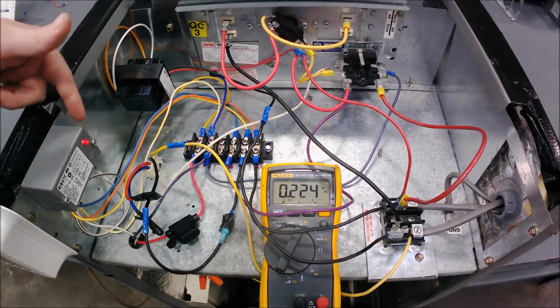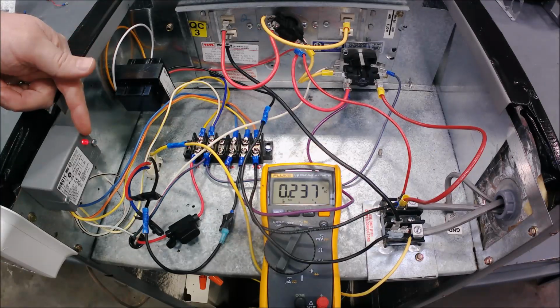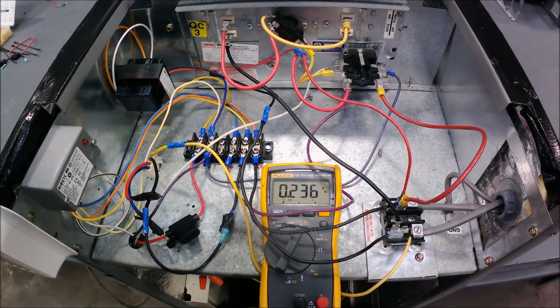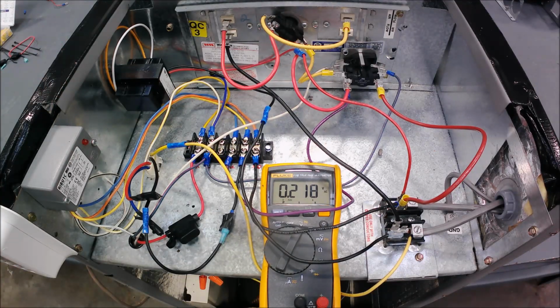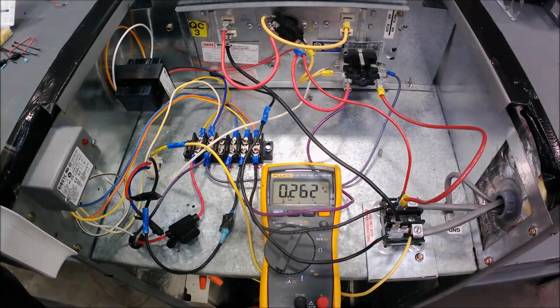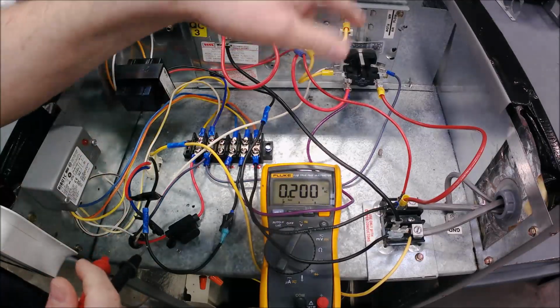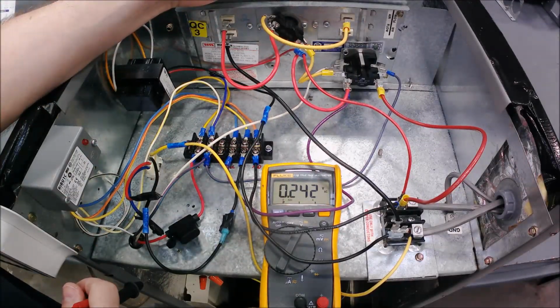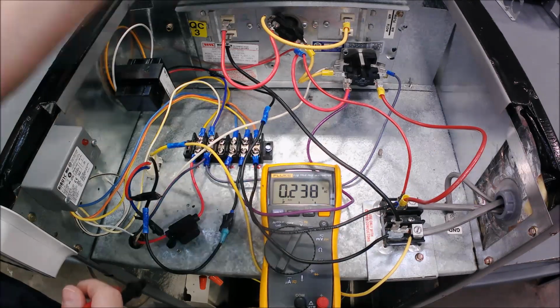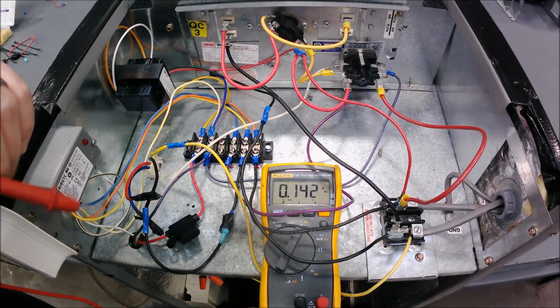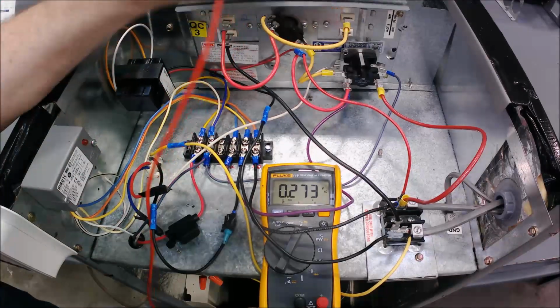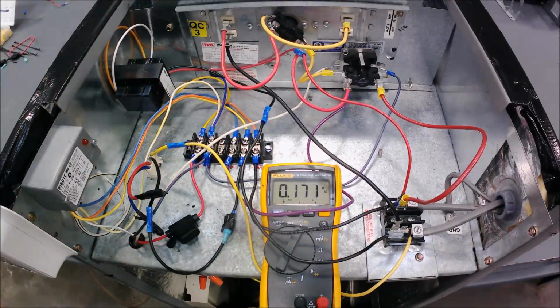Alright, and the red light's still on. And there we go. So now I'm going to turn on the heat, make sure it works that way. I've got this set up for a one-stage heating, and the thermostat is programmed so that the fan is operated by the system, not operated off of the G necessarily in this case. So we're going to let that, if I check, oh, there it goes.